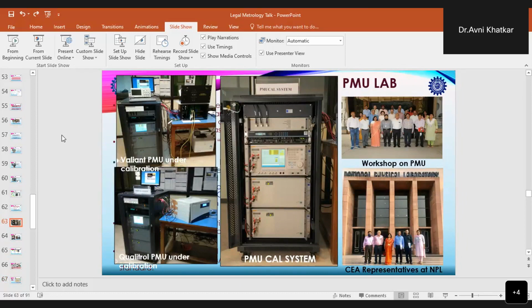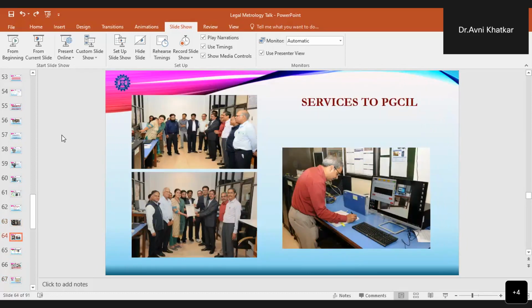So we have this PMU calibration system. We are providing services to different manufacturers for their PMU calibration. Also, different representatives generally come from CEA in order to see what this system is and how it can be used for the nation. We are also providing calibration services to PGCIL. Recently, we calibrated PGCIL's PMU calibrator system, which can be further used to calibrate all the PMUs. So that system is also now traceable to the national standards of the country.